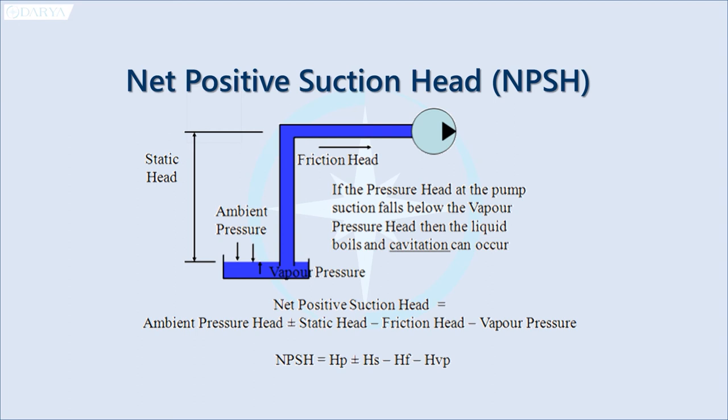Net positive suction head is equal to ambient pressure head plus or minus static head minus friction head minus vapor pressure.